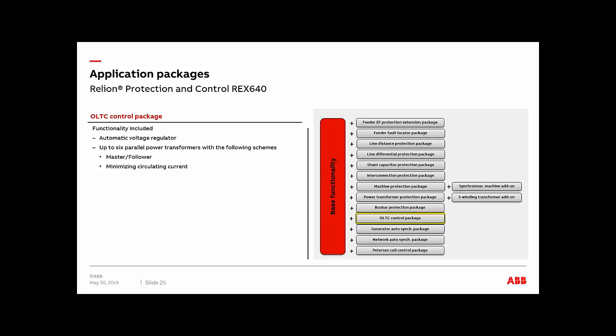Now the master follower scheme does require GOOSE communication between the controllers of the transformers that are being paralleled. So you do need communication via GOOSE for this specific scheme. Then you're going to have the minimizing circulating current scheme, and this one could be used for transformers that are not exactly the same, that are different in impedance and number of taps. In this one you also need communication between the controllers so you can implement the minimizing circulating current scheme.